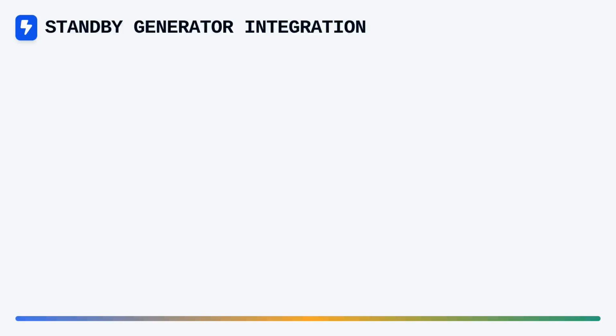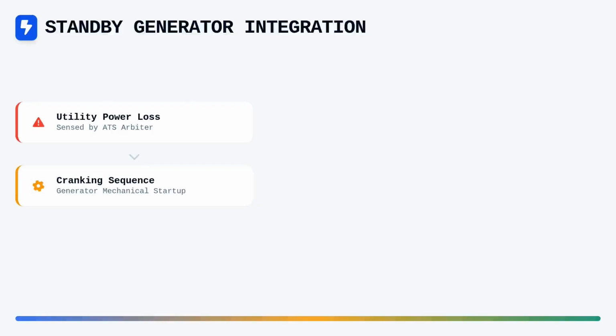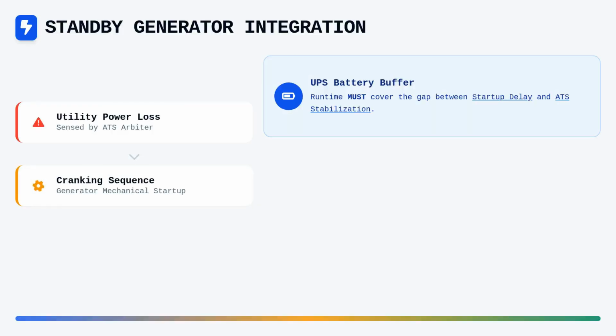The integration of a standby generator introduces a different set of engineering constraints, specifically regarding fuel supply and mechanical startup time. The automatic transfer switch serves as the intelligent arbiter of power, sensing the loss of utility voltage and initiating the generator's cranking sequence. You must ensure that the UPS battery runtime is long enough to cover both the generator's startup delay and the stabilization period required for the ATS transition.